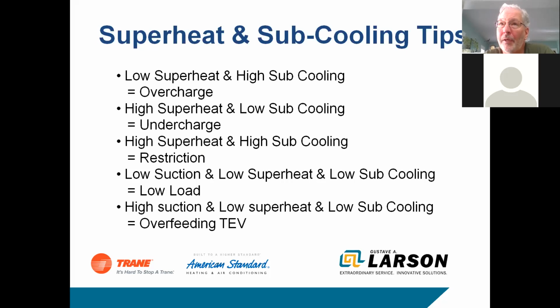Before you change an expansion valve, it's not a bad idea to take a temperature reading of the suction line at the outdoor unit and the indoor unit, and the liquid line, also outdoor unit and indoor unit. Make sure they're the same temperature. If your temperature outside is say 100 degrees on the line and it's 70 on the inside on the liquid line, you've got a restriction. It's flashing off somewhere. So make sure you don't overlook restrictions. Dryers are plugged at 3 degrees, so if you have a temperature drop of more than 3 degrees, that dryer should be replaced also. These are things to look for when you're troubleshooting these systems that you can catch pretty quickly.